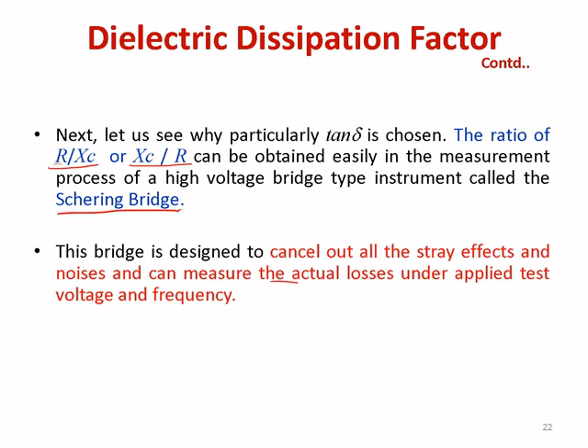And this is the pictorial or schematic representation of the Schering bridge. This is just like a Wheatstone bridge type thing, but here we want to measure the tan delta of this equivalent series resistor and capacitor under test, and we are measuring this capacitor with the help of a standard capacitor with negligible equivalent series resistance. At balance conditions the tan delta value is omega C3 into R3 in terms of these two parameters. Here we show the series equivalent representation of a lossy capacitor, but similarly we can measure the parallel equivalent capacitor also. This is the standard method of measurement of tan delta by using a Schering bridge, which is basically designed for high voltage in the kilovolt range.